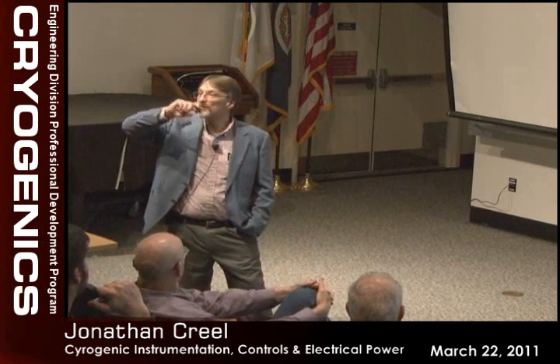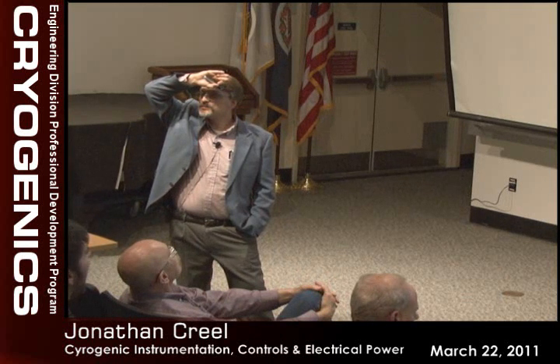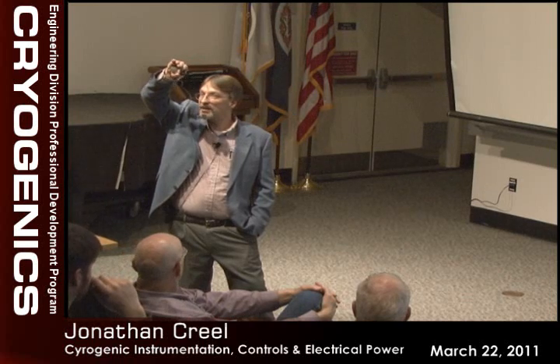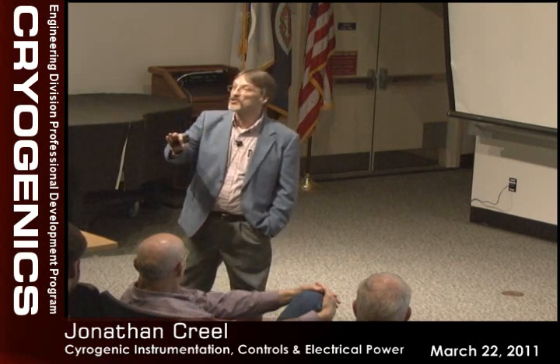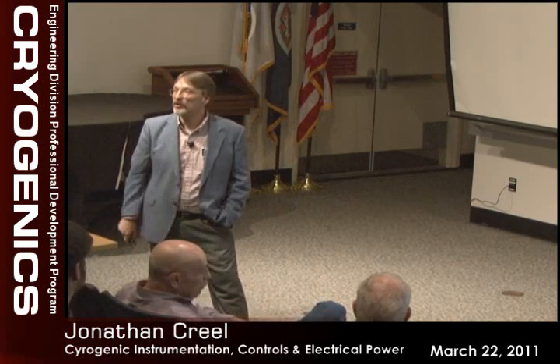A couple of real quick questions. No wave modulation? You didn't try any wave modulation? No, we didn't change any of that. You didn't shape the VFD's wave? Yeah, you can change the shape, you can change the frequency, and we did not do any of that. That's one of the areas we want to look at.